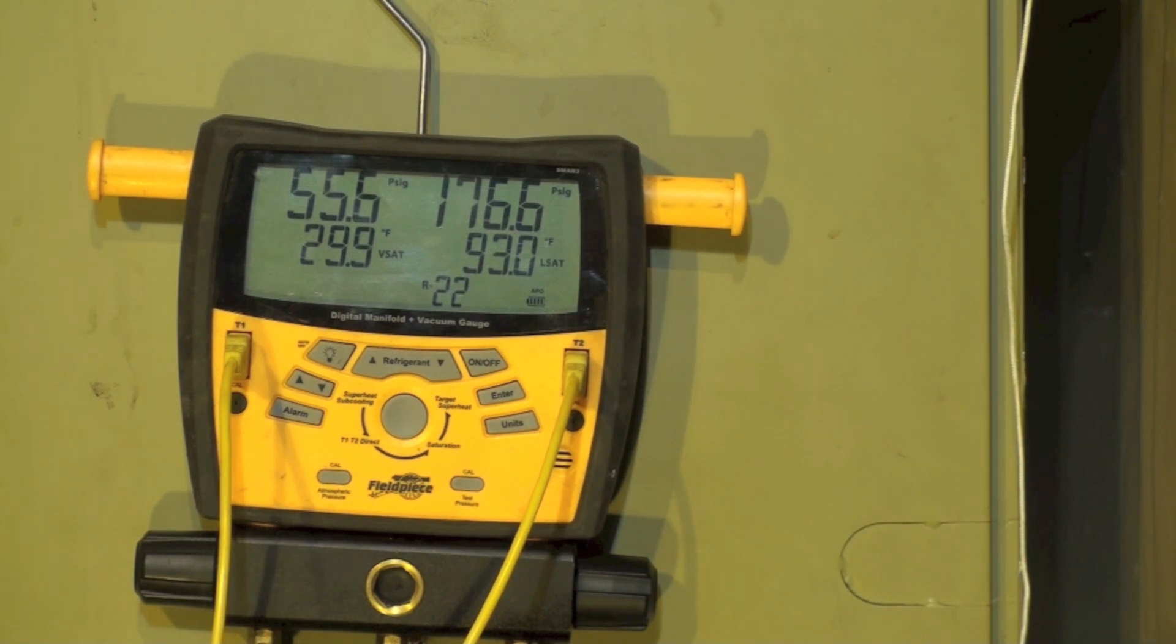Now what I'm going to do, I'm going to go back to superheat and subcool. This is a fixed orifice device machine. Although even if it was a TXV machine, the reactions would have been the same on the first video. Let's find out if it is refrigerant charge.